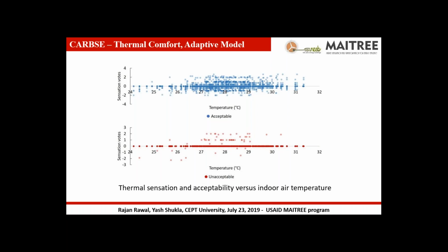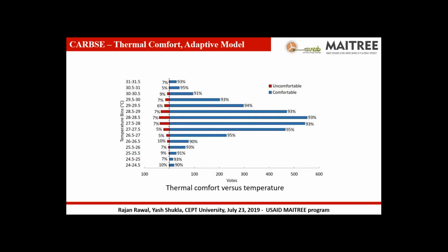So most of the people who said that the temperature for some reason is unacceptable had an almost neutral vote. So this is where we had to look into saying that even though the temperature is meeting the requirement, do you still have to increase the air velocity? Do you have to have the pedestal fan in the building so we can increase the acceptability of our building? And the blue dot shows on the top what is the range of the thermal sensation votes we have observed in the building.